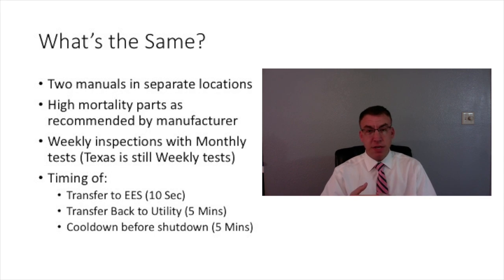The timing's the same. 10 seconds, 5 minutes, 5 minutes on the cool down, unless you have an air-cooled prime mover that's 15 kW or less, and I've only seen one of those in the last 4 years, so I don't think you have one of those.